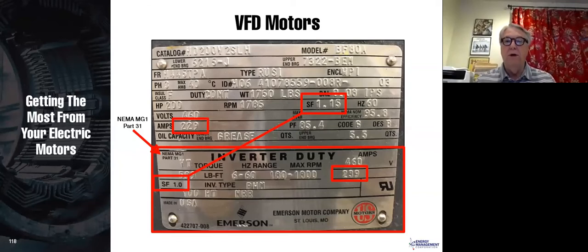And any motor that is VFD rated will have a spec that says you can run this speed range on a variable torque or this speed range on a constant torque. And typically, if you have a good cast iron TEFC motor with 1.15 service factor, you can run that over a 4-to-1 speed range with a constant torque load like a conveyor. You can run it over a 10-to-1 speed range with a variable torque load. Now, the full load amps remains the same unless the manufacturer tells you differently.